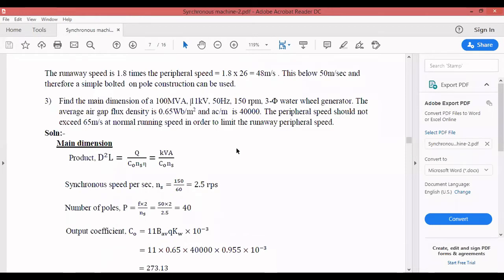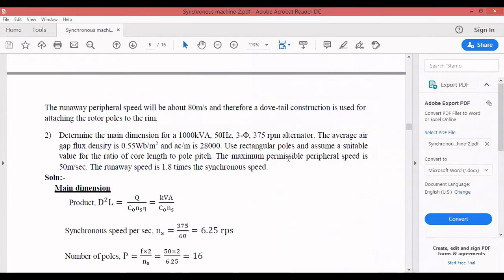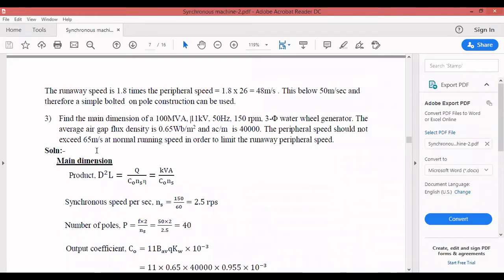The problem does not specify which type of rotor pole to use. Since we have circular poles (L/τ: 0.62–0.7) and rectangular poles (L/τ: 1–5), we make an assumption and then verify by calculating the peripheral speed. If it is within 65 m/s, the assumption is correct; otherwise, we switch to another pole type. I assume circular poles with L/τ = 0.65.